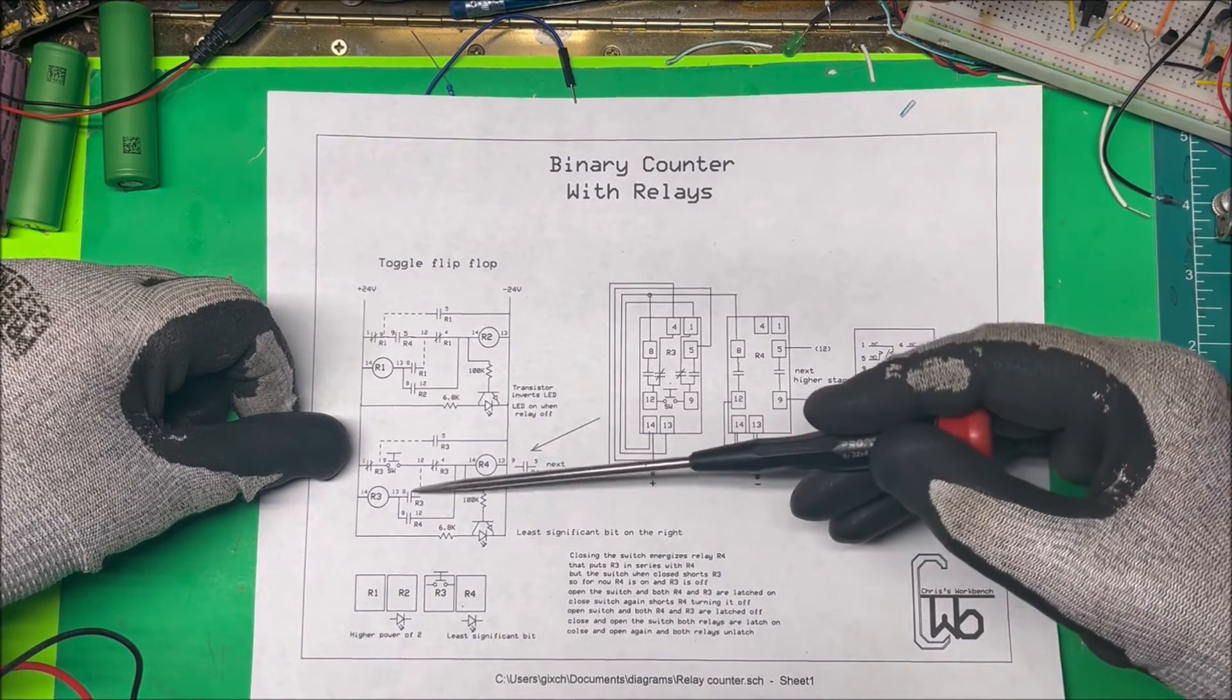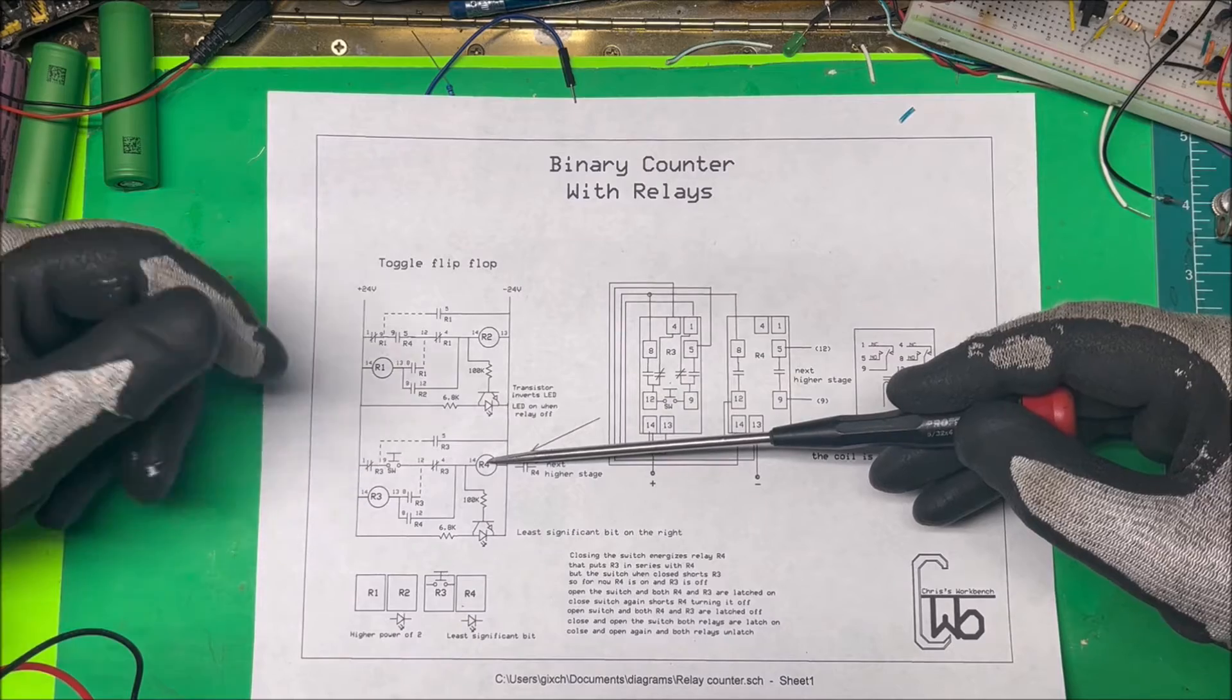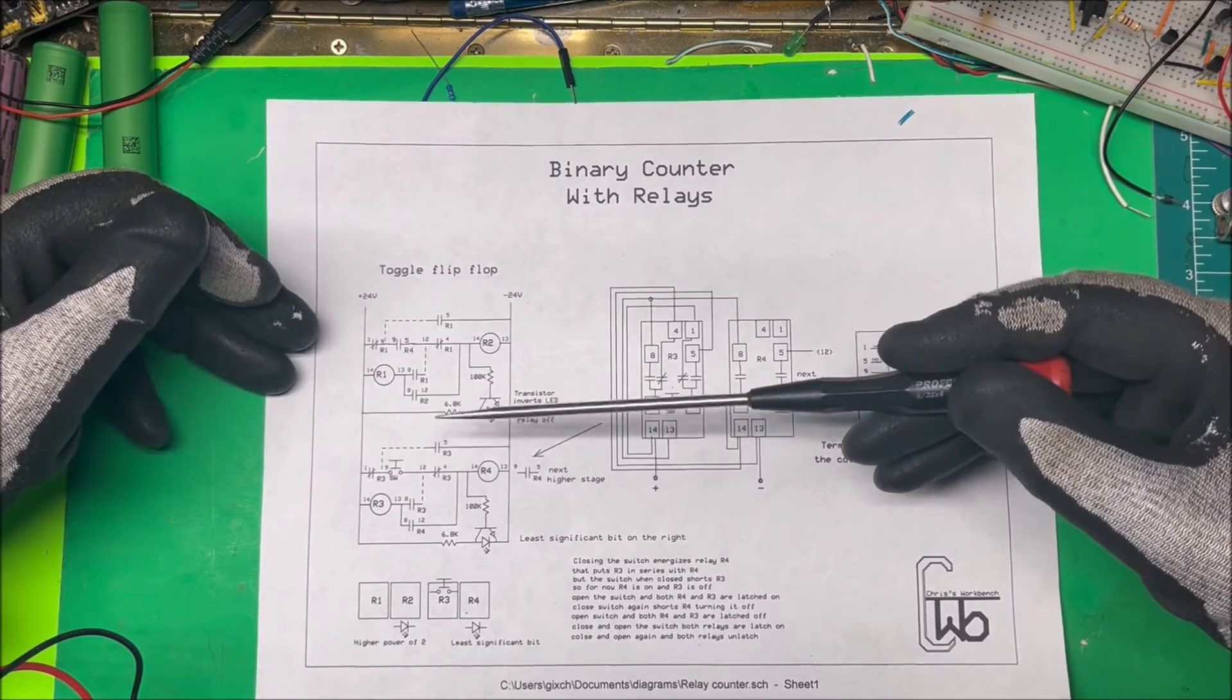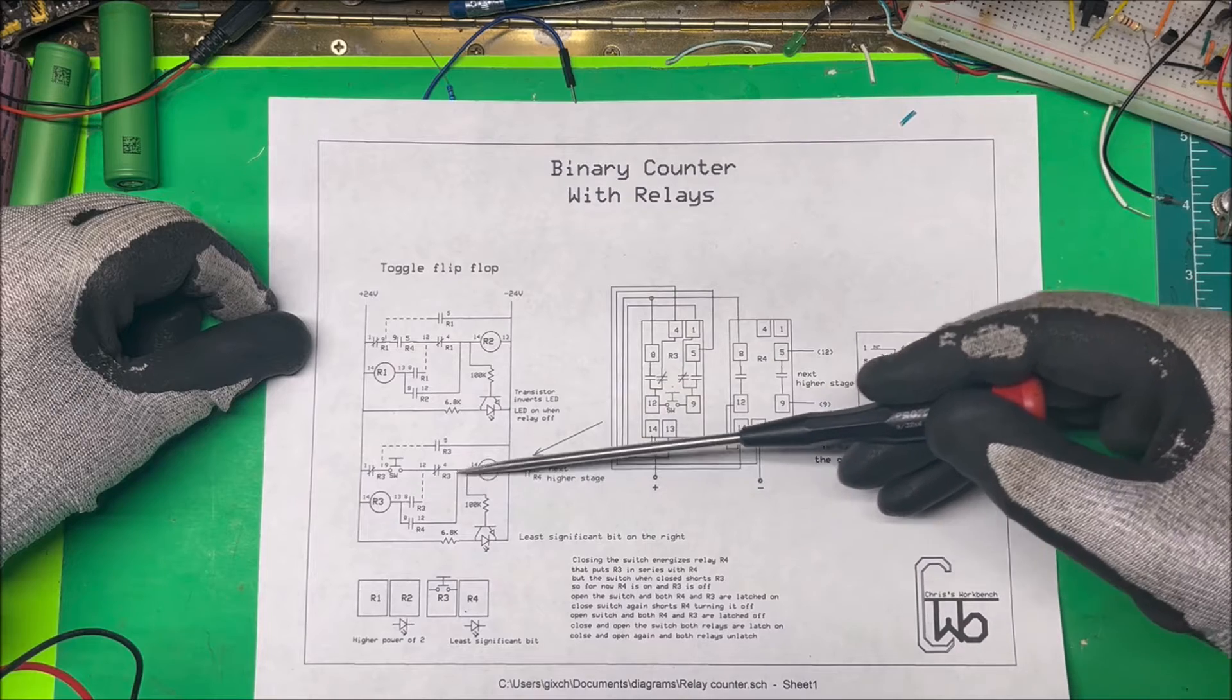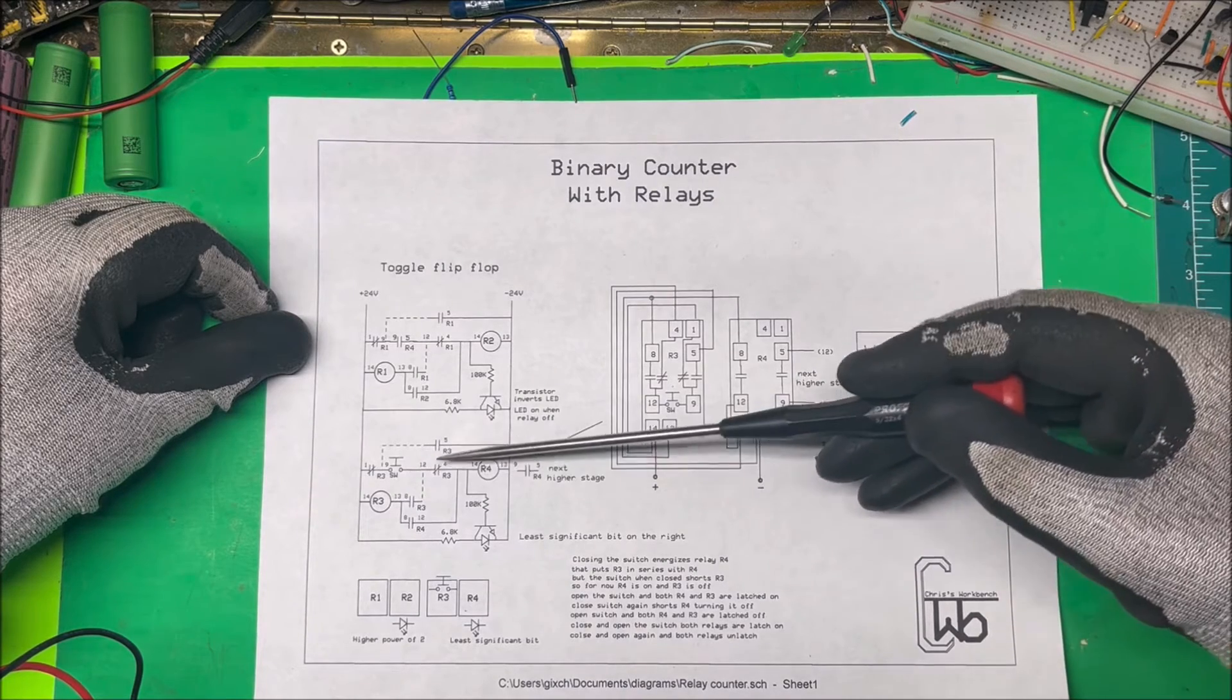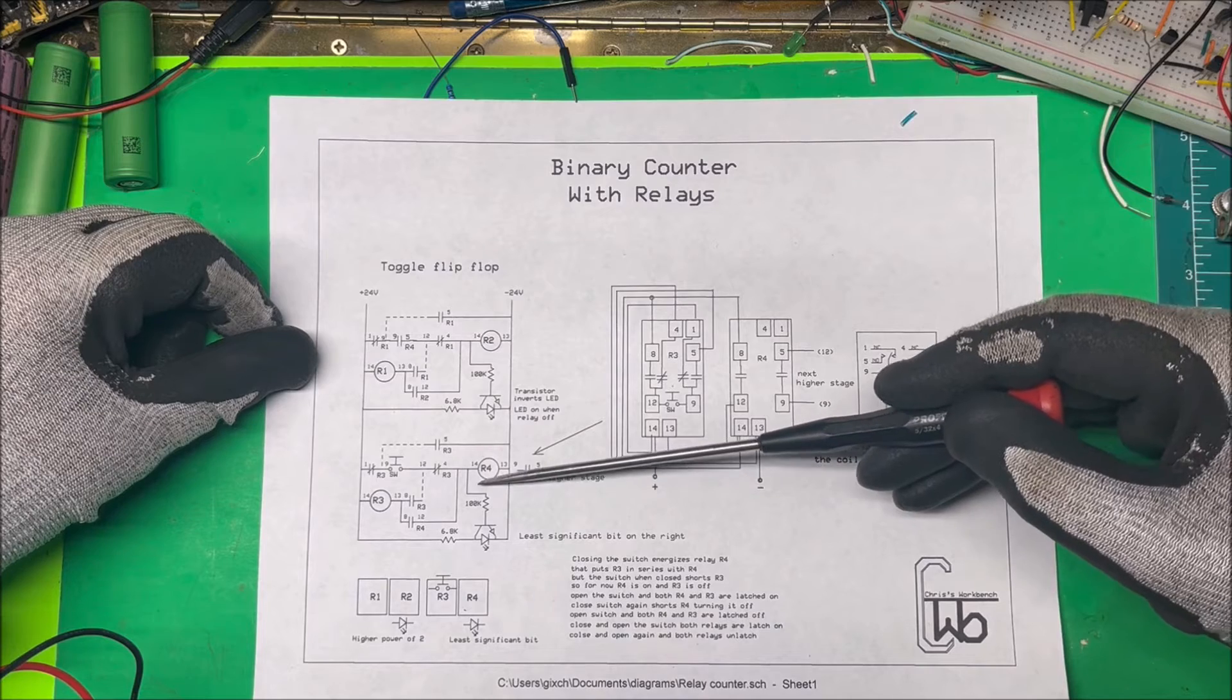What happens here is when we close the switch, it energizes R4 and that puts R3 in series with R4. But when the switch is closed, it shorts out R3 here. This is going to be shorted out through here, so for now R4 is on and R3 is off when this is depressed. But when you open the switch, both R4 and R3 are latched on. Then these are going to be both latched on. You close the switch again and it shorts out R4, turning it off. And we open up the switch, both R4 and R3 will be off. So how it works is we close and open the switch, both relays are latched on. We close and open switch again, and both relays are latched off. So it's just going to be a flip-flop toggle. Either they're going to be both on or both off.